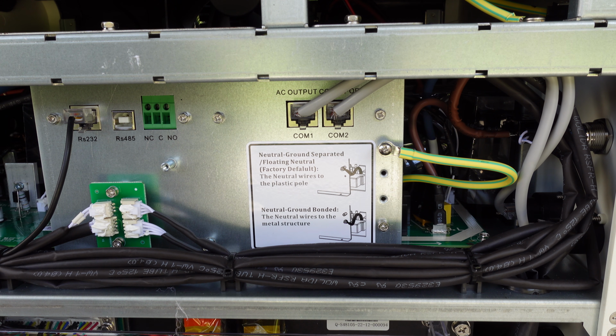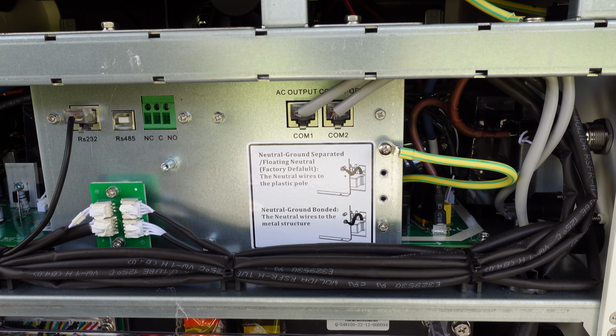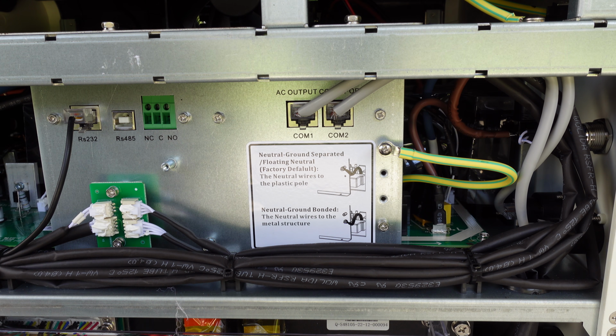This is fine under most operating circumstances, especially if you're using this as a portable unit. However, there are times when you may want the neutral and ground bonded. In standard US power, that's typically the case, and it's typically only done at one location—your main service panel or main disconnect, wherever that may be.